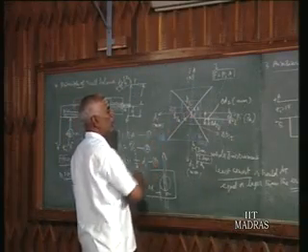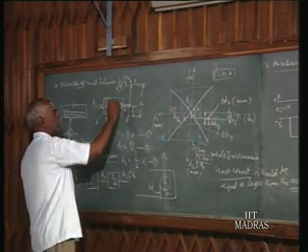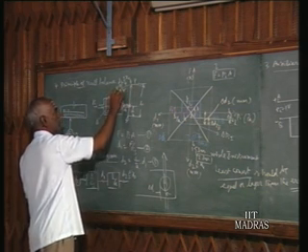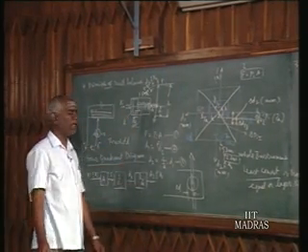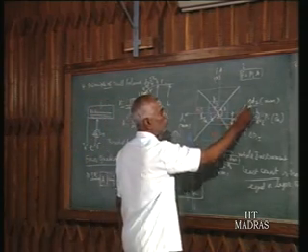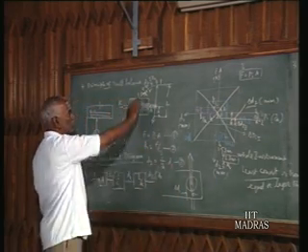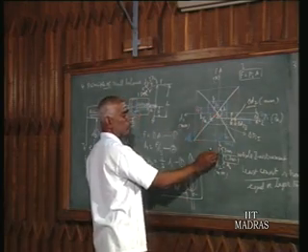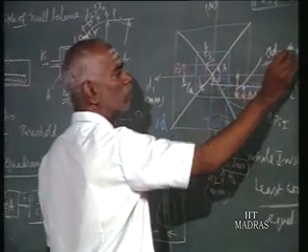For this 2 bar, there is also another condition in international practice: for this least count we should have a minimum distance of 1.5 mm between two graduations, so that we don't strain our eye when we take a reading. So how to check whether there is 1.5 mm or not? That is our delta D2. For the error of 1.5 bar, which it was before selecting 2, what is the distance, that is delta D2? How many millimeters is there?